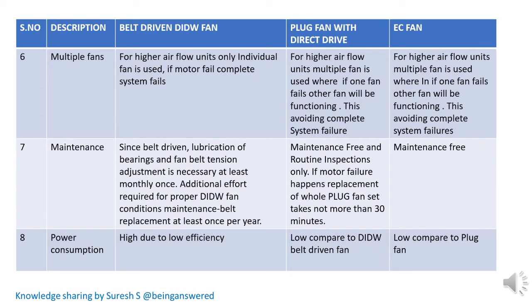In belt driven fan, we can't have multiple fans — only one fan can be used, and if the motor fails, the complete system will fail. Whereas in plug fan and EC fan, we can use multiple fans. Even if one fails, the other fan will be functioning, thereby avoiding complete system failure.